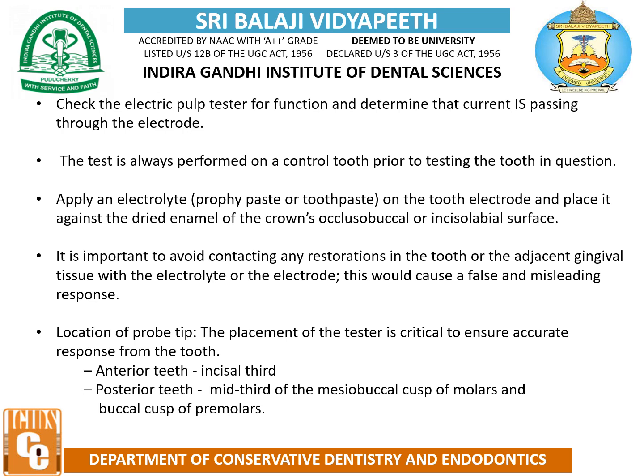Location of the probe tip. The placement of the tester is critical to ensure an accurate response from the tooth. For the anterior teeth, the probe tip should be placed in the incisal third. For the posterior teeth, it should be placed in the mid-third of the mesiobuccal cusp of molars and the buccal cusp of premolars.